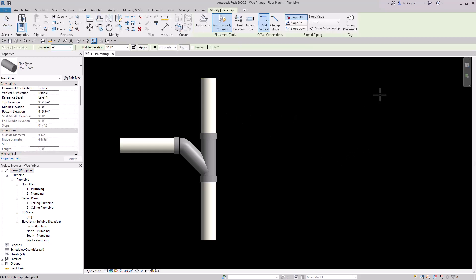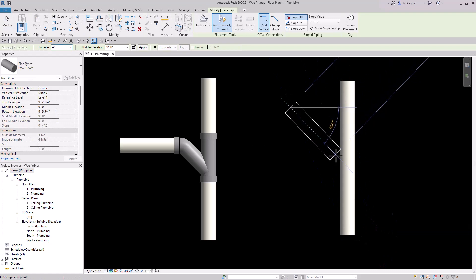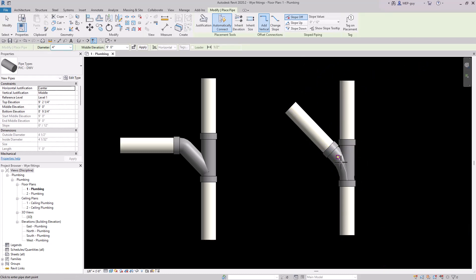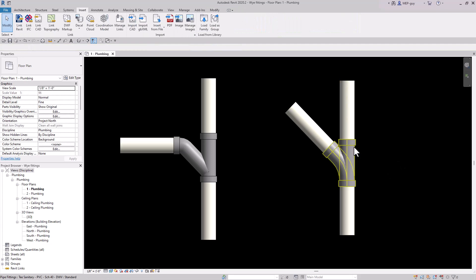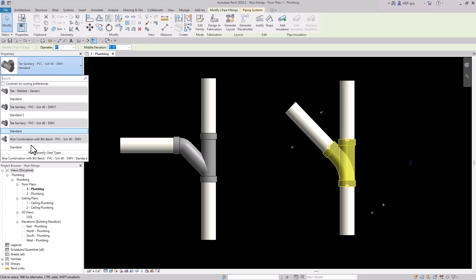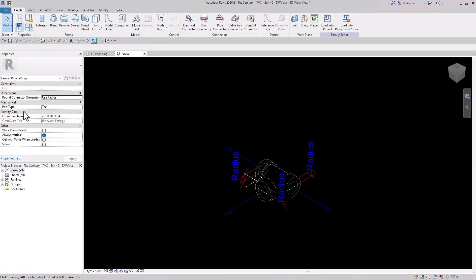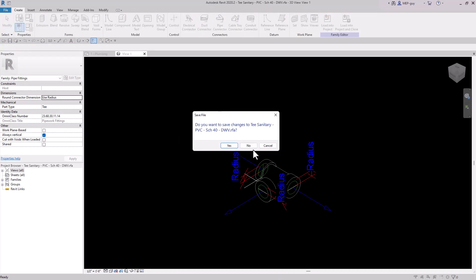Let's draw some more piping and try to Y into it — you can see it still uses the sanitary tee. If we click the dropdown and try to select the Y fitting, it's not available on the list. The reason is this is actually a tee-type fitting. If we click on it and go to Edit Family, you can see under Part Type it's actually a tee fitting — so we can't use the Y fitting directly.